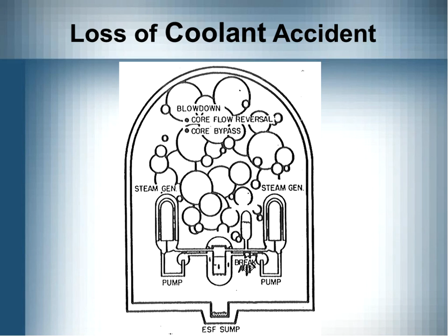These are the systems we use to reflood. We've got a number of systems, about half shown here, in the ESF building, with two trains for redundancy—one train on emergency power supply, and a complete identical set for backup. If we had a break in the coolant line, the first thing to kick in would be the accumulators—large pressurized cylinders filled with nitrogen and water. As the pressure in the system drops, they start blowing water into the coolant system and the reactor core to keep it cool.